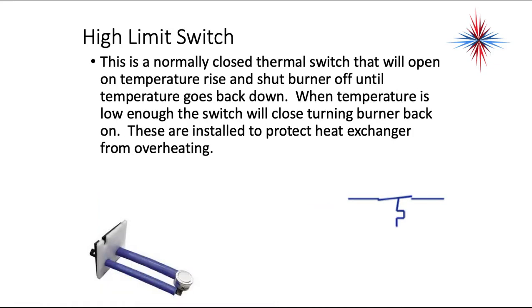A high limit switch is basically the same symbol. It's a normally closed thermal switch that will open on temperature rise and shut the burner off until the temperature goes back down. When the temperature is low enough, the switch will close turning the burner back on. These are installed a lot of times to prevent the heat exchanger from overheating or prevent fire.